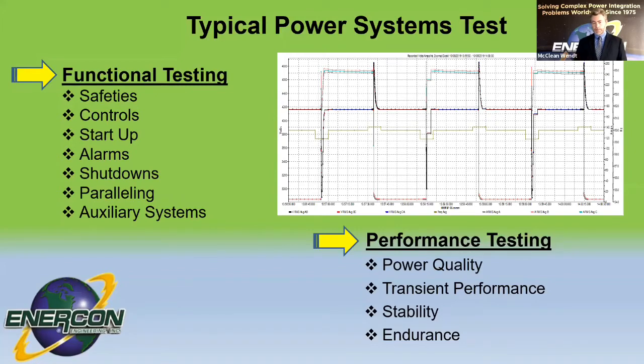So moving from just the pure functional testing, then we want to also look at the performance of the power system. And for those, we'll be looking at the metering on both the current and voltage, all three phases. And we'll have a power quality analyzer that we can check waveform, harmonics, any of those things that are fundamental to the generator of the power system itself. When you're doing that testing, typically you want to run that on just purely resistive load bank, so you're not having an effect from your reactive load bank. And you're just characterizing the generator under test.